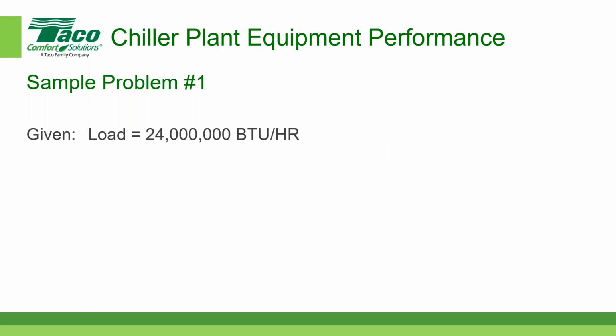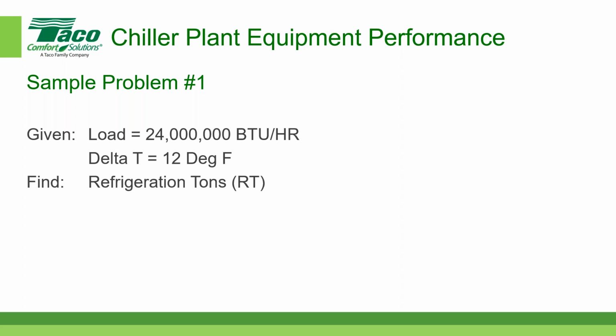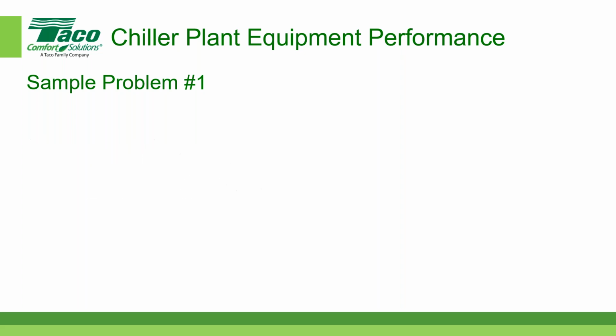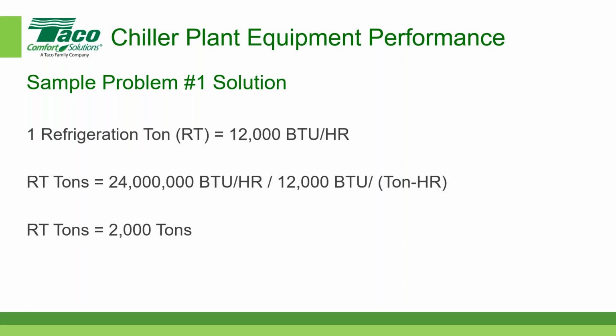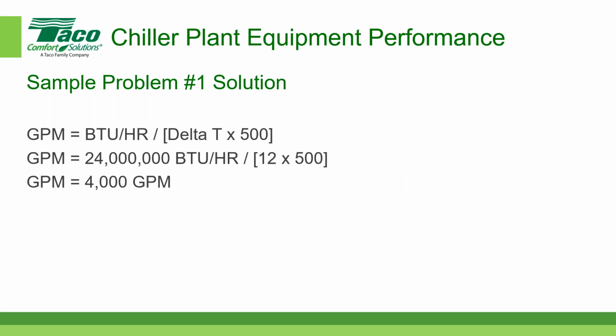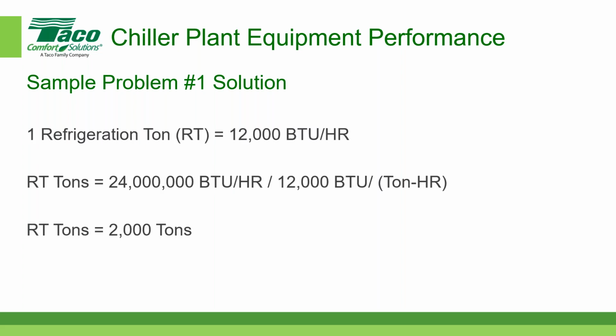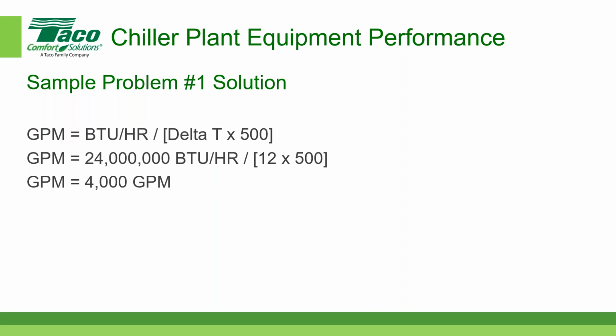So I'm going to skip over this. Let's just go through it quickly. I want to be careful of our time here, because we want to go into the piping after we go through the cooling towers. So if we have 24 million BTUs per hour and a delta T of 12 degrees Fahrenheit, remember I said it should come out to 2 GPM per ton? Well, the total GPM we're looking for: 1 ton of refrigeration is 12,000 BTUs per hour, so we have 2,000 tons. If we plug that into that other equation we talked about earlier, it comes out to 4,000 GPM. For 2,000 tons, 2 GPM per ton, it's 4,000 GPM.